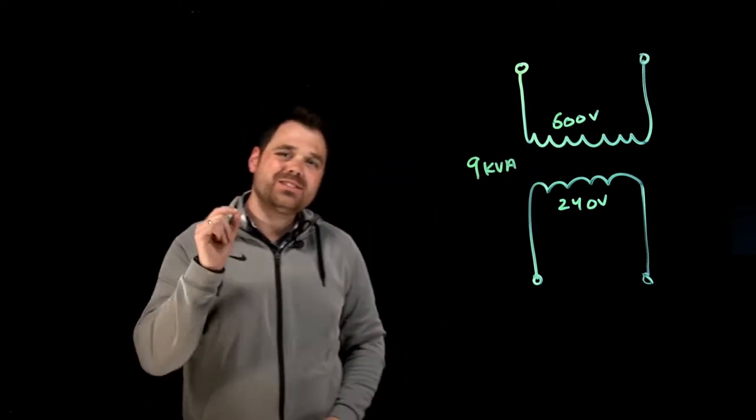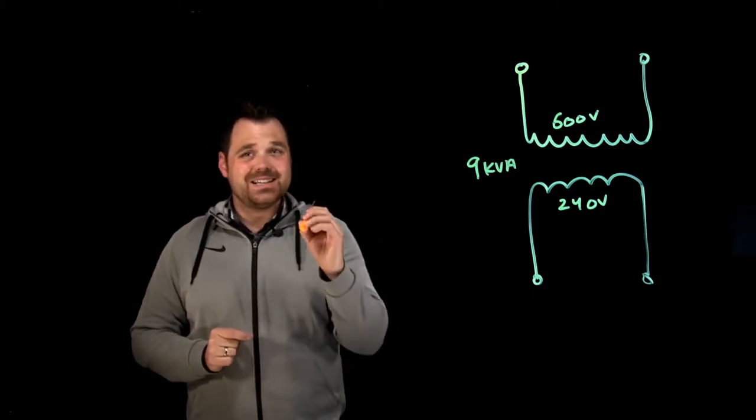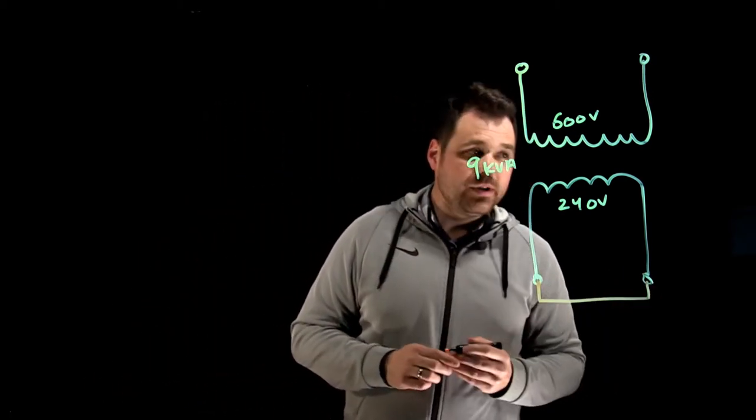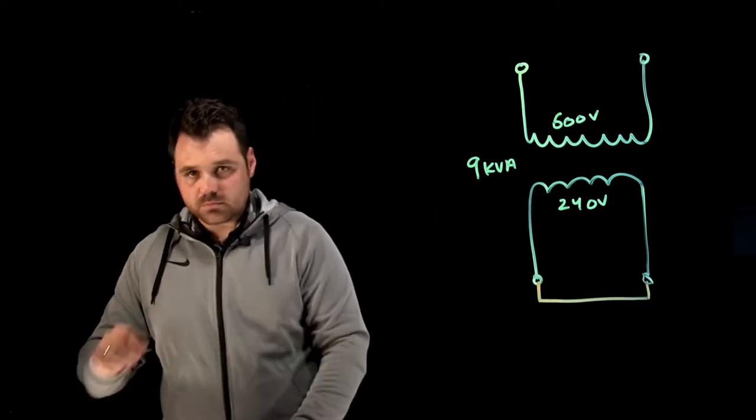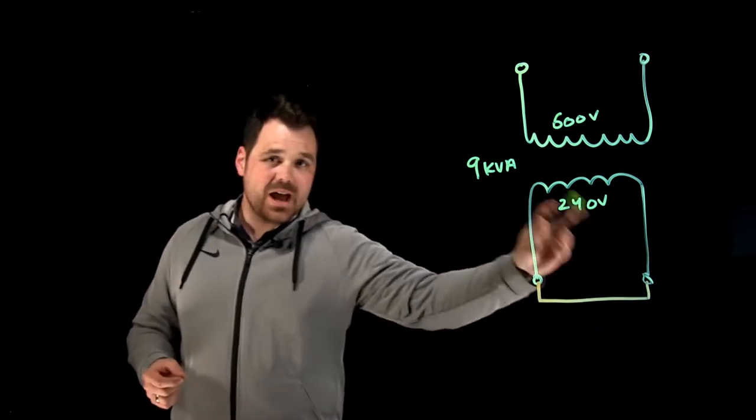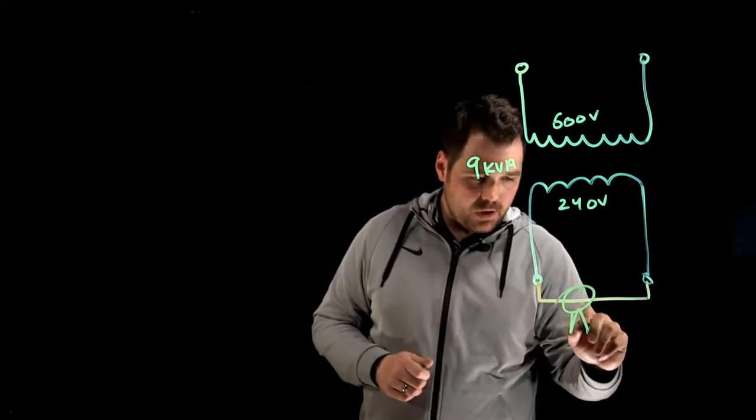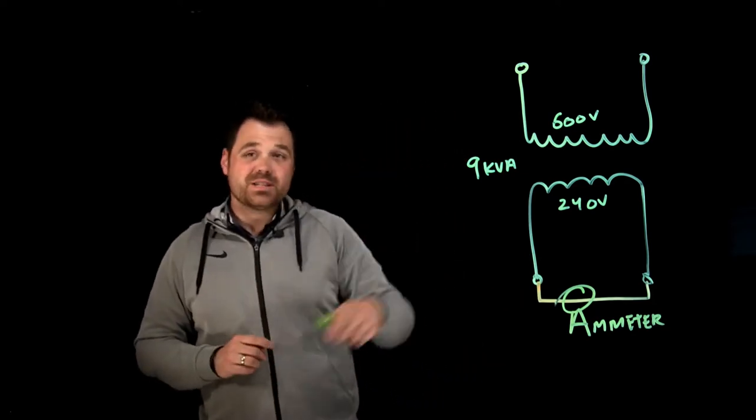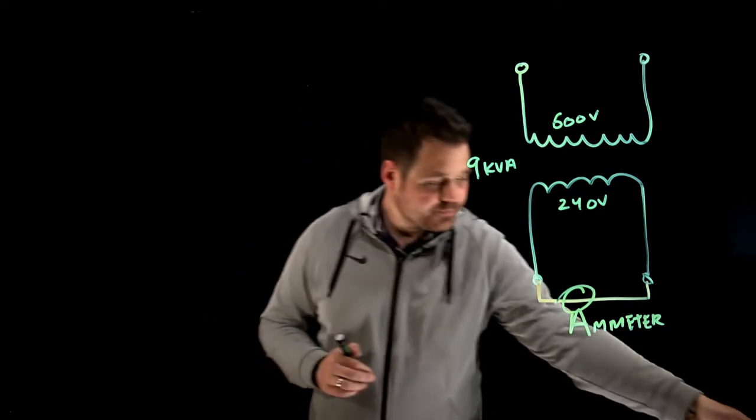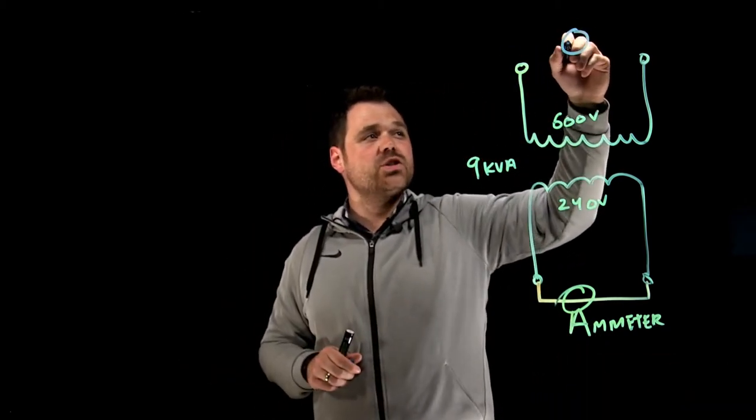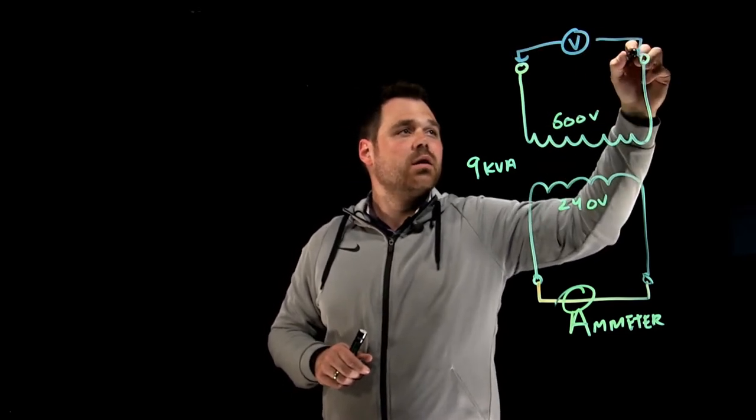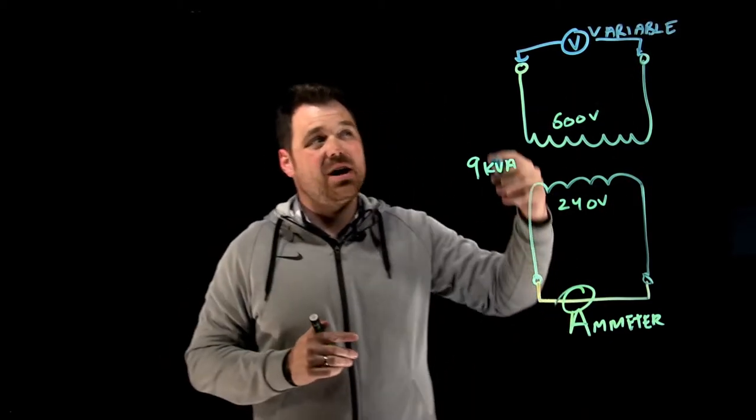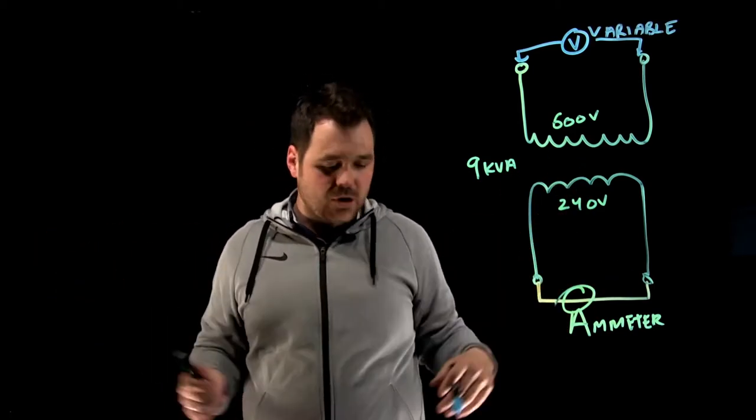So what you do in order to calculate your percent IZ or your percent impedance is you do what's called a short circuit test. So I'm literally going to short circuit my secondary. So I short circuit my secondary, just like that. And I take my ammeter. Now, what I'm waiting for on my ammeter is my rated current. What I do on my primary is I'm going to take a variable voltage. So this is a voltage supply and it is variable. Now, with that short circuit, obviously, if I applied rated voltage, I would have huge current, I'd burn out my transformer. But what I want to do is on this ammeter, I'm looking for my rated secondary current.